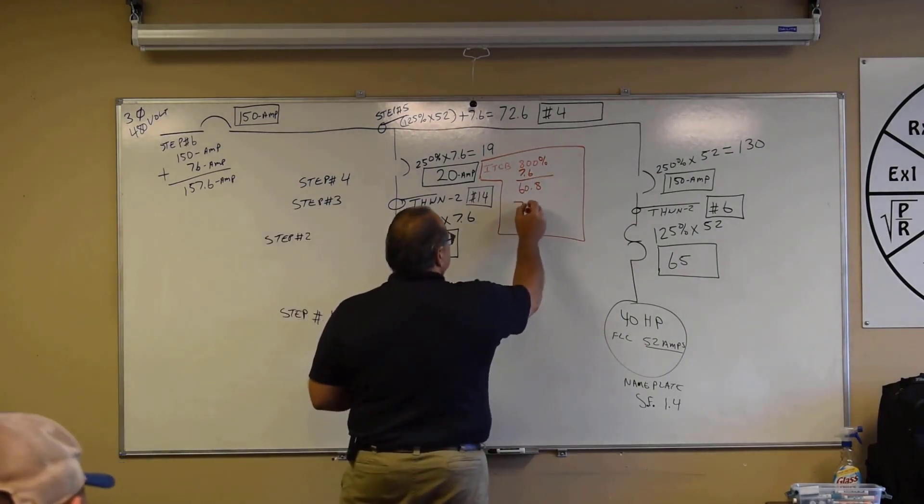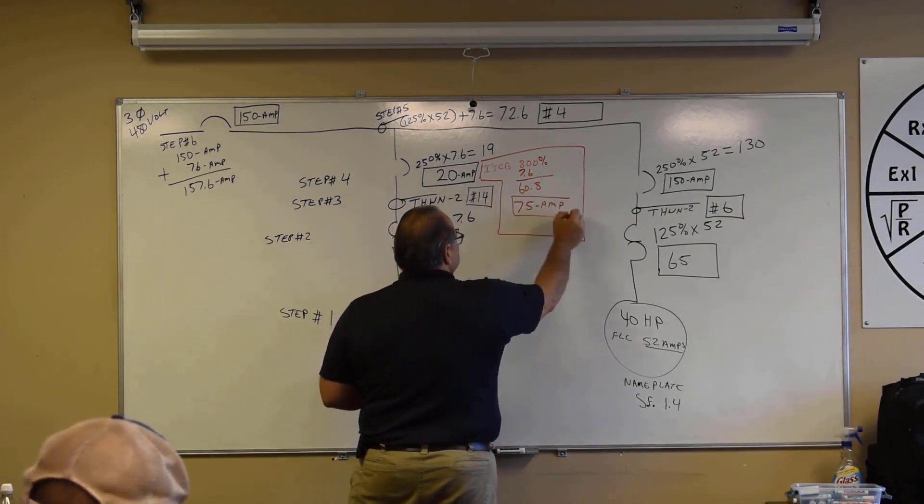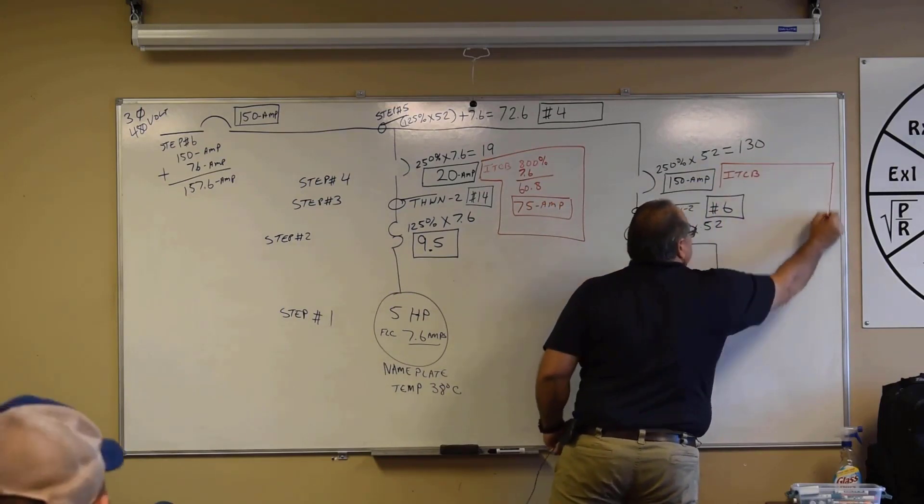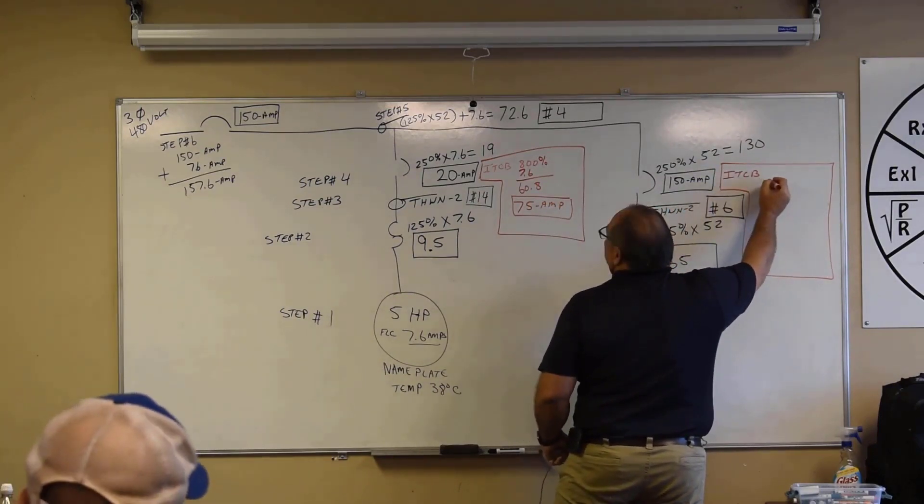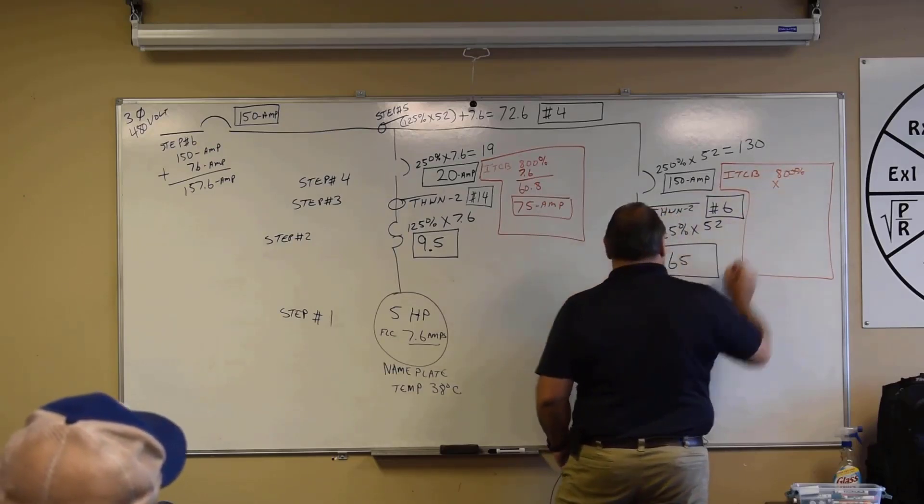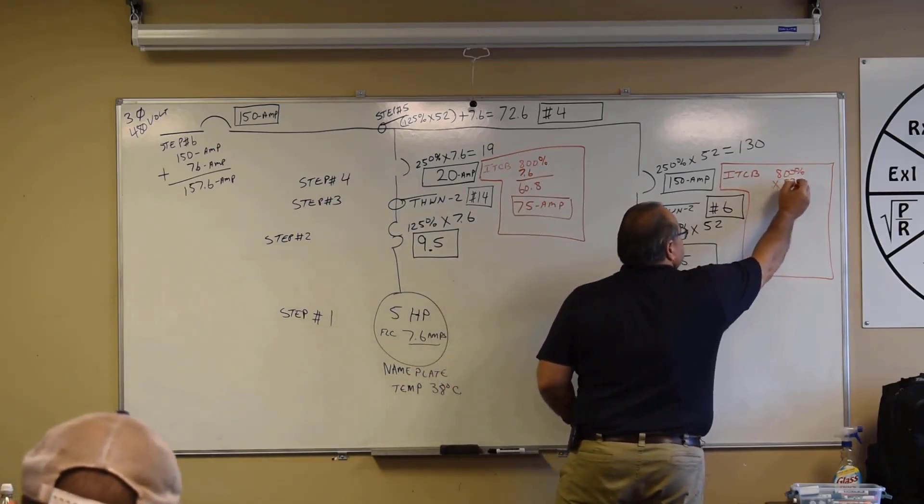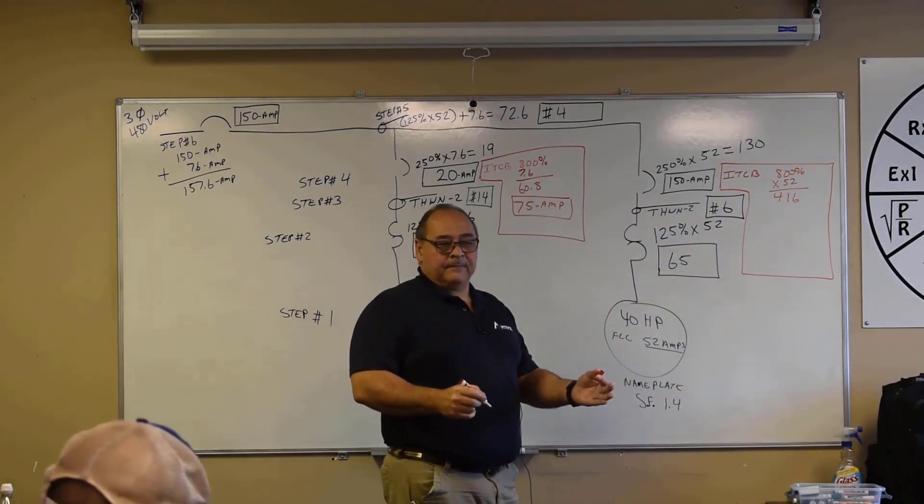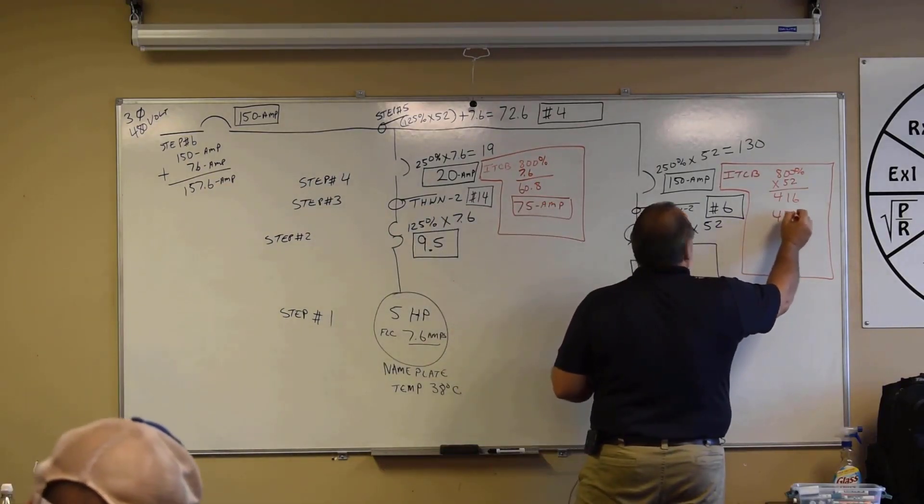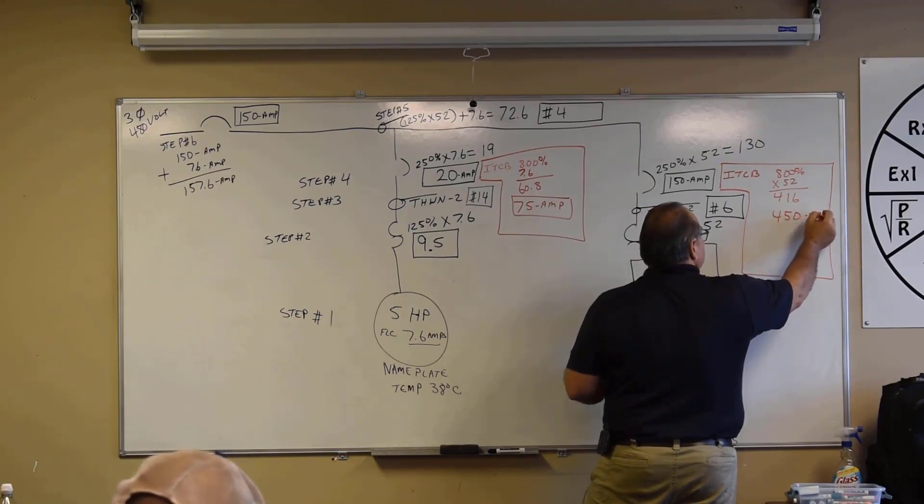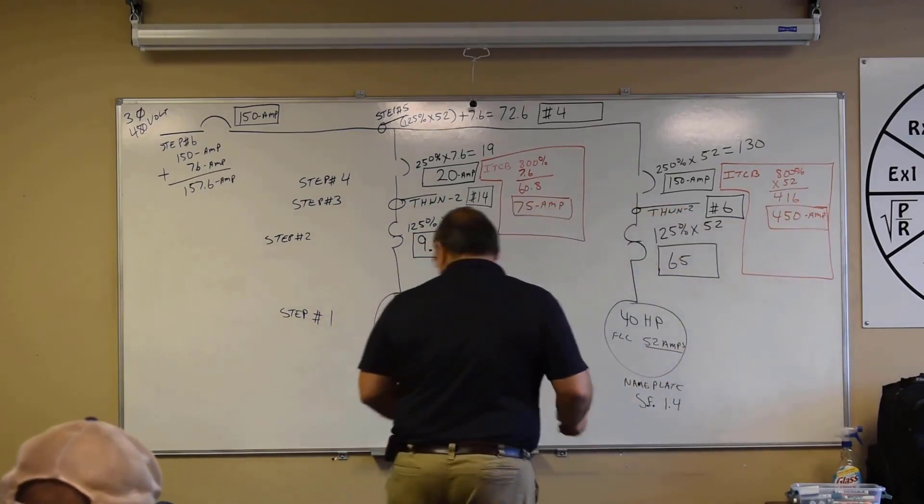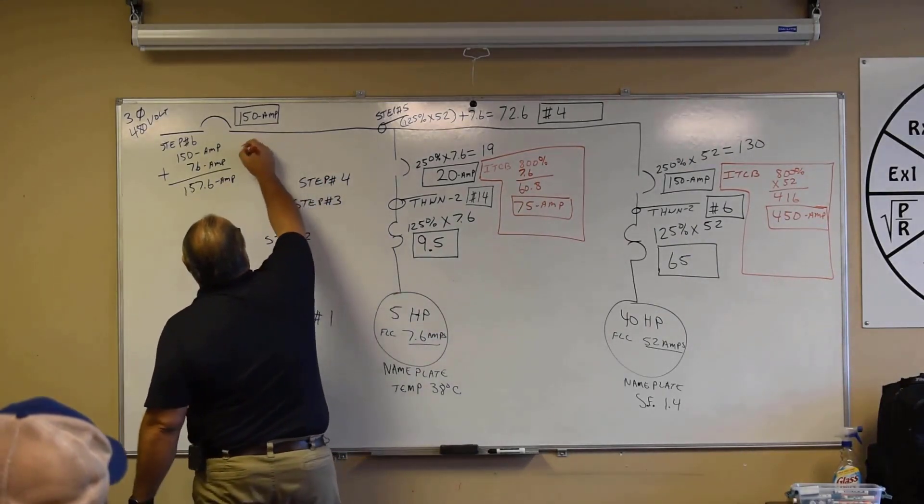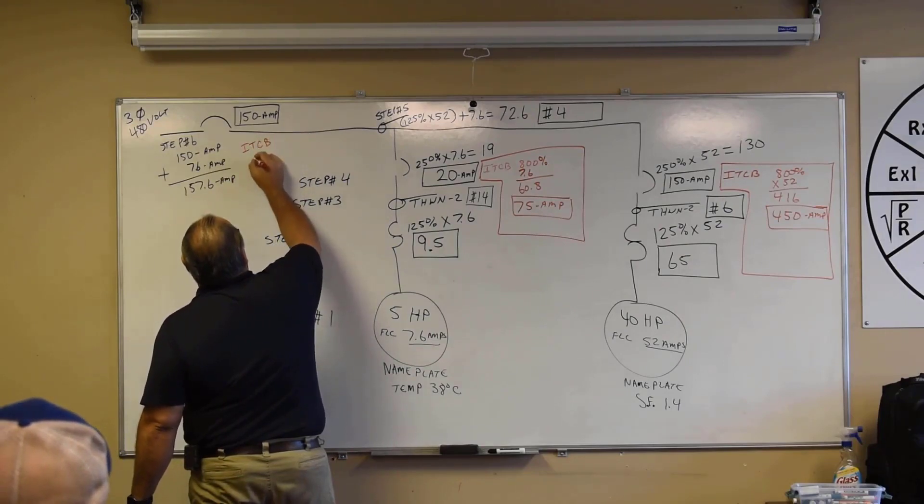Okay, over here we've got instantaneous trip circuit breaker. And again it's 800 percent, and again it's 800 percent, right? Times in this case 52 amps. 416. And we're allowed to go up. What's 416 goes to? 450, right? So 450. And then obviously on step number six, if we took 450 and added 7.6 to it, we can't go up. This one up here is going to be instantaneous trip circuit breaker. It'll also be 450, right?